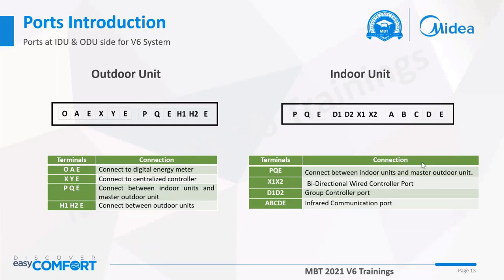Before we go into details about each controller, let us understand what kind of ports we have on the outdoor unit and indoor unit side. For the outdoor unit, we have the OAE port, XYE port, PQE port, and H1, H2E port. XYE port connects to the central controller or the BMS gateways. OAE port is for connecting the DTS 343 energy meter. PQE connects to the indoor unit side, and H1, H2E is for connecting outdoor units in parallel connection.